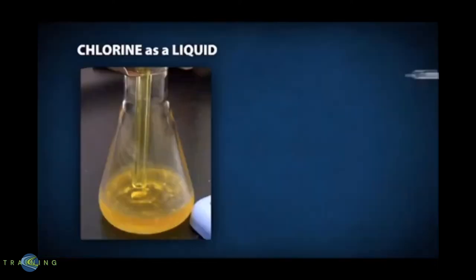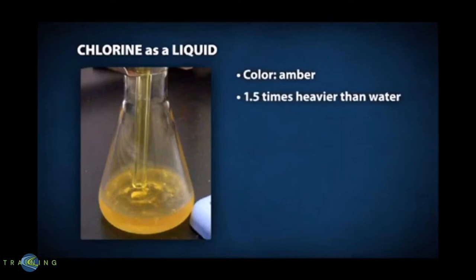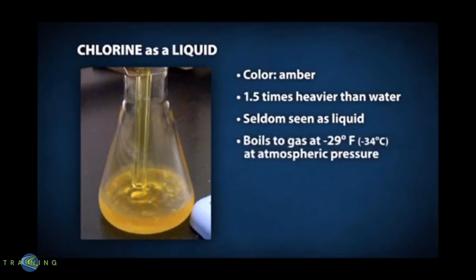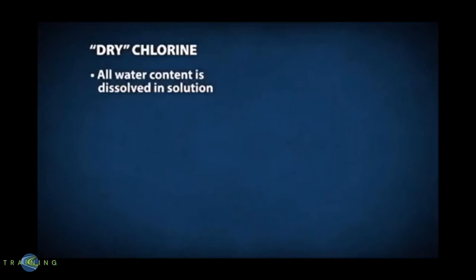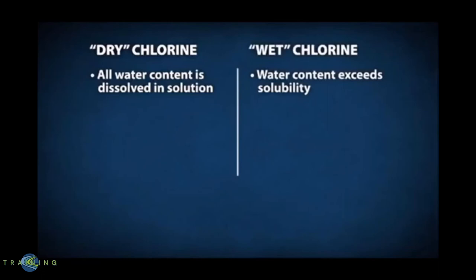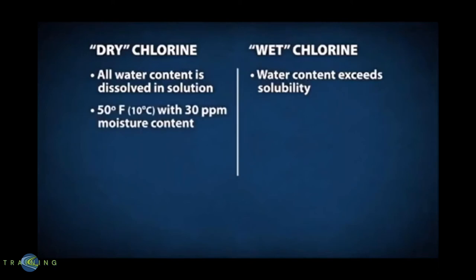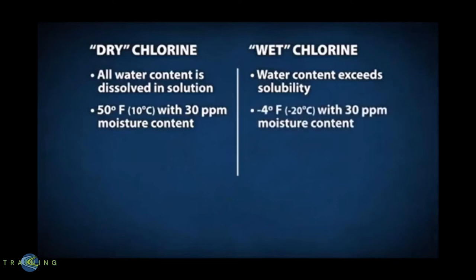As a liquid, chlorine is amber in color and about 1.5 times heavier than water. Chlorine is seldom seen in a liquid state because it converts to gas at minus 29 degrees Fahrenheit at normal atmospheric pressure. When chlorine is shipped, it has very low moisture content and is referred to as dry chlorine. Dry chlorine has all of its water content dissolved in solution. If the water content exceeds its solubility, it would be defined as wet chlorine. At 50 degrees Fahrenheit, chlorine with 30 ppm moisture content would be dry, while at minus 4 degrees Fahrenheit the same moisture level would make it wet chlorine.